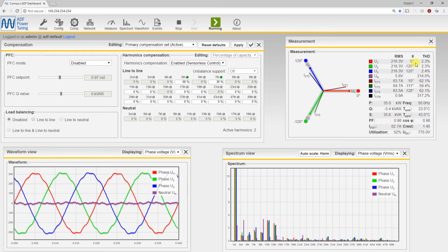We're now already at 2.3% on the voltage distortion. There's still a little bit on the 11th and 13th. We can just put a little bit of percentage to compensate on the 11th harmonic as well. We drop the 11th harmonic a little bit down, and also the total voltage distortion drops a little bit. This is already enough in this particular case to run the active filter. We don't need much more than that to compensate. So you see in sensorless control, typically the values that you add in the settings here are much smaller than the settings that you would add in current control. And typically also it's not that many harmonics that you activate.